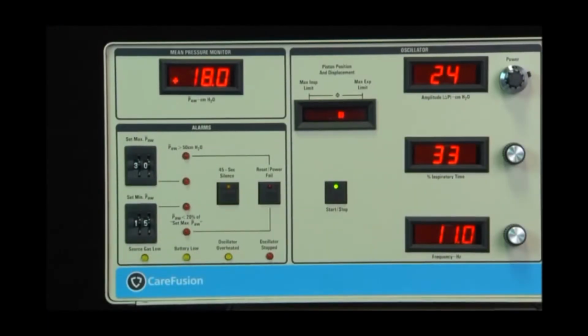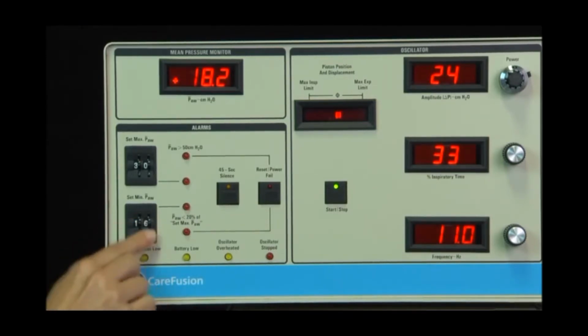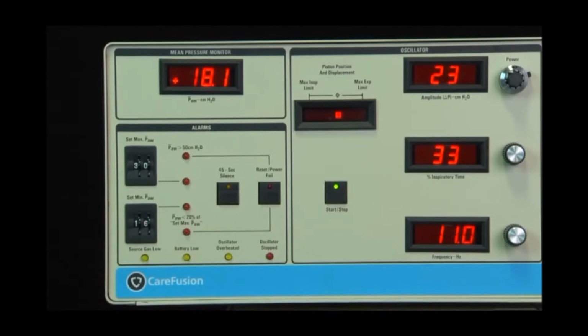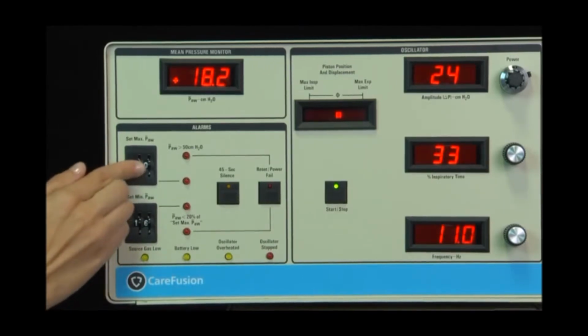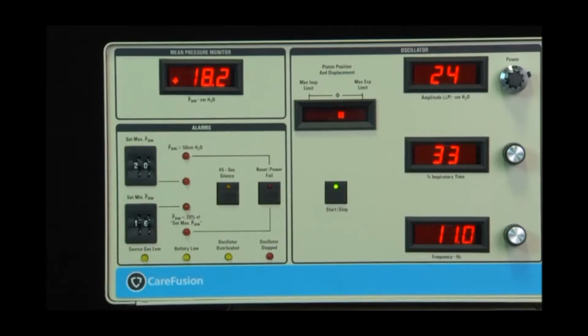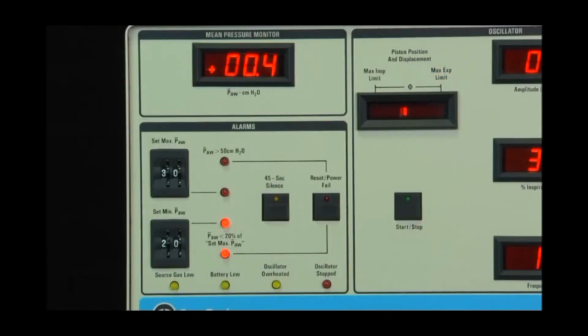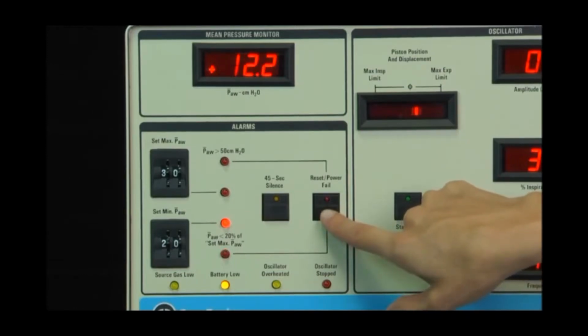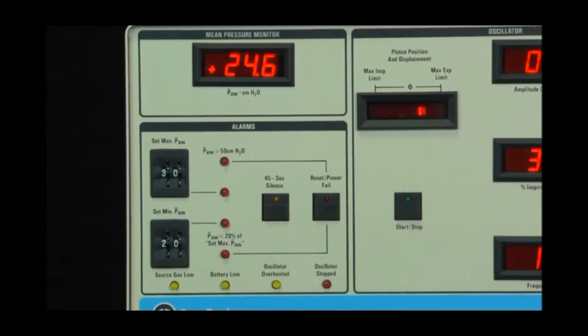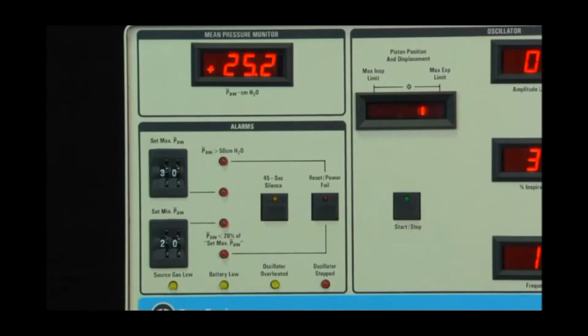Alarms. Thumbwheel controls are used to adjust the set maximum and set minimum mean airway pressure alarms from 0 to 49 centimeters of water pressure. The set maximum mean airway pressure will provide an audible and visual signal when the alarm threshold has been reached. If the alarm for the set minimum mean airway pressure is triggered, audible and visual alarms are activated. The audible and visual alarms automatically reset upon resolution of the fault condition. Activation of the backup mean airway pressure alarms will also trigger audible and visual alarms.